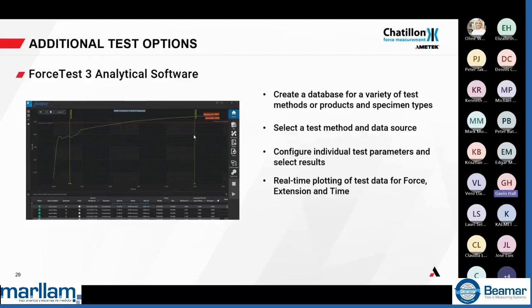So you can see on screen here, we can actually have multiple ranges to detect peaks, and as I say, you can have multiple ones here. So if you have a particular peak here, we can analyze here, but we can also get the values over here. So yes, it can be configured to give you multiple areas.